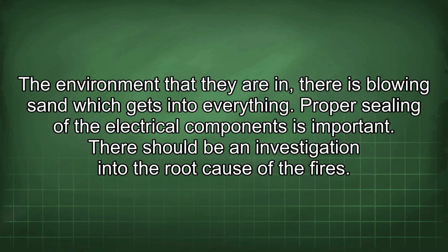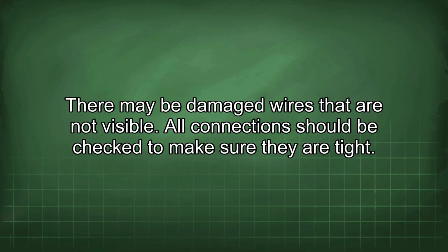The environment that they are in, there is blowing sand which gets into everything. Proper sealing of the electrical components is important. There should be an investigation into the root cause of the fires. There may be damaged wires that are not visible. All connections should be checked to make sure they are tight.